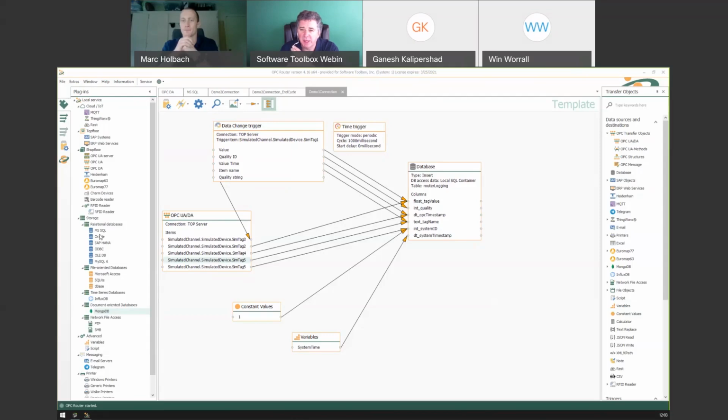Okay. Someone else, Mark, has asked, and I know the answer, but you're the instructor, so you can answer it. What about industrial protocols like EtherNet/IP, Modbus TCP, and Profinet? So those are not supported directly through the OPC router. This would be the next stage up. You would still need an OPC server, or something that translates it to OPC, sitting between. This would not go to those devices directly.